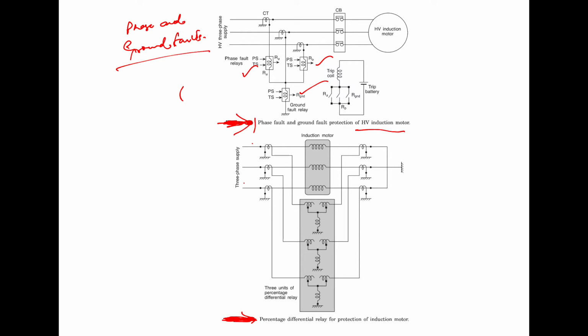Ground faults. Now, for a high impedance ground fault inside the motor, the fault current may happen to be less than the full load current. So such faults are difficult to detect using the overcurrent approach, and for that we use the current balance type of protection, which we can discuss in this lecture also.